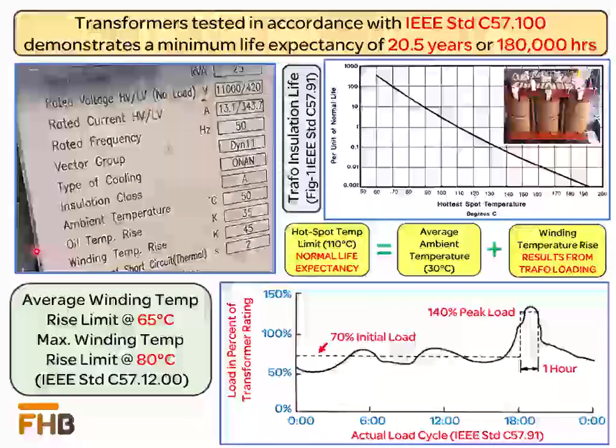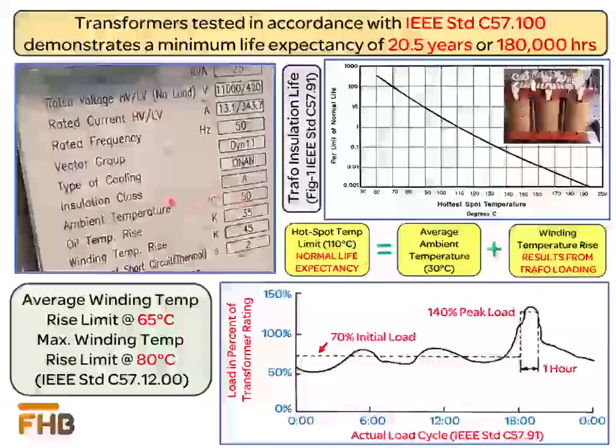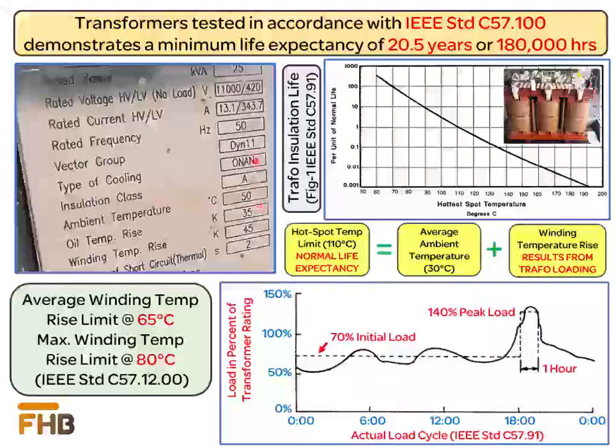The limit of temperature rise is the factor which decides how much a transformer can be overloaded beyond the nameplate rating. This is because when the loading of the transformer increases, the temperature of the winding and the oil which is in contact with the winding also increases. This results in thermal aging of the transformer insulation. It is important to note that temperature is not uniform in all spots of the winding. The winding spot where the temperature is maximum is called the hot spot temperature or the hottest spot temperature.